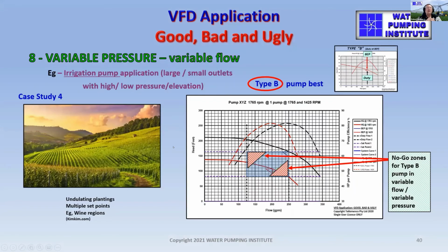What about a combination of variable pressure and variable flow? Well, it's really a combination, and you might recall we had a no-go zone for a variable flow and a no-go zone for a variable pressure. So if we combine these variable pressure, variable flow situations, you'll finish up with both of those no-go zones, and it's safe to operate the pump in the rest of this area as far as flow and pressure goes. And you might have situations like that in an elevated site where you have multiple outlets, and the outlets are of different flow sizes, and that's all by design, of course. So if you're going to design an irrigation system to be run on a VFD, it might be prudent to actually size those outlets according to what you're going to be able to achieve when you run that with a VFD, and it needs to be inside this zone and not include the red bar zones.